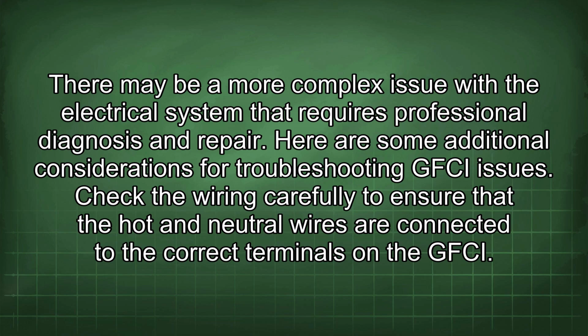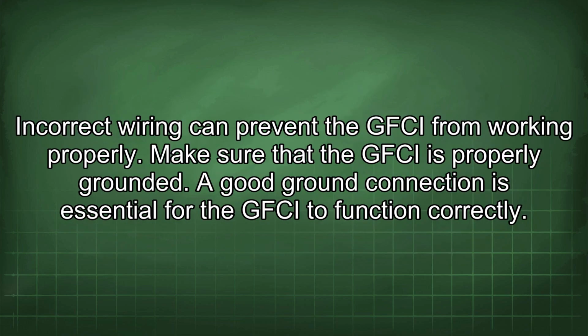Here are some additional considerations for troubleshooting GFCI issues. Check the wiring carefully to ensure that the hot and neutral wires are connected to the correct terminals in the GFCI. Incorrect wiring can prevent the GFCI from working properly. Make sure that the GFCI is properly grounded. A good ground connection is essential for the GFCI to function correctly.